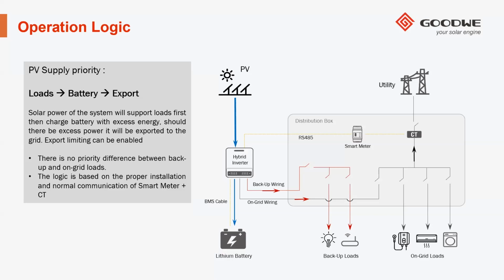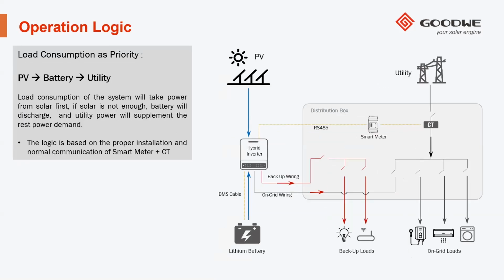So with our hybrid inverters, our PV supply is always a priority, regardless of the work modes you use. So the solar power of the system will always support the loads first and then charge the battery with excess energy. Any excess energy can then be exported to the grid if export limitation is not enabled. Also, with our hybrid inverters, there's no priority difference between backup and grid connected loads. It sees all loads as a priority and tries to cover them. So load consumption is the priority.